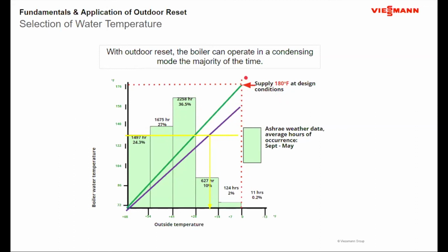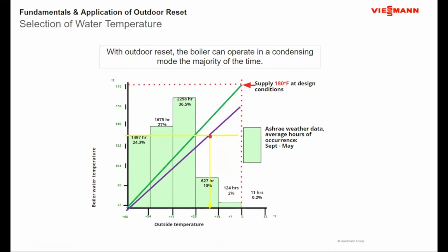So if I do outdoor reset on the design day, I might only be delivering 86.5, maybe 87% efficiency. But when the outside temperature gets in the neighborhood of about 22 degrees Fahrenheit, 20 degrees Fahrenheit, all of a sudden the return water temperature crosses that dew point, and now I'm starting to condense. And you look at this, and from an aspect of condensing, the boiler may not condense on the design day, but from an aspect of performance, that boiler's condensing for greater than 90% of the heating season.